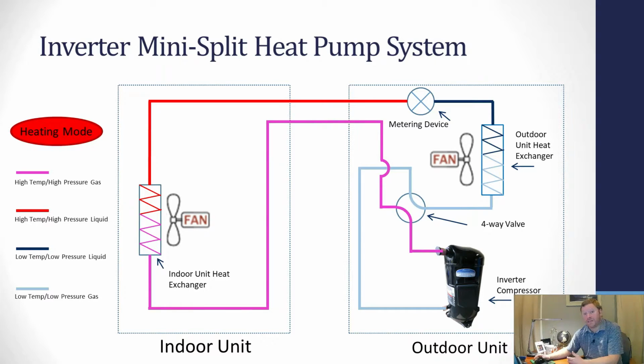And to give you an idea of what that looks like on a traditional heat pump system, you might lock out your heat pump at 40 degrees, 45 degrees. If it's a 16 SEER or 2-stage, maybe you go down to 35 degrees, but that's still seldom. With an inverter heat pump system, you can run that year round all the way down to 0 degrees. And on some systems, depending on manufacturer, you can actually go below 0 degrees outside, and the system can still get heat energy out of the outdoor air. It's pretty cool. So looking at the schematic, nothing's really changing.